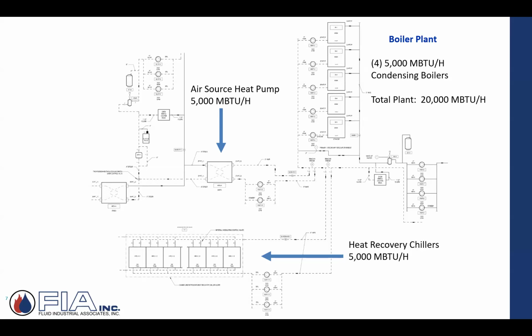Well, we'll get into it later on, but primary, secondary, tertiary, this can support boiler plant, air source heat pumping, the pumps dedicated to the heat recovery chillers, and then there'll be some type of control sequence on how to make this all work. So this is, 5, 6, 7 years ago, this picture wouldn't have been up on the board here. We weren't doing this. We weren't talking about it that much. Now, this is every day, every week, every month. This is happening, especially here on the eastern seaboard, whether it be Mass or Connecticut, Rhode Island, New Hampshire, et cetera, Maine. So anyways, these are some of the different design systems. They're very basic drawings up on a board, but this is how they start. And then we get into designing them.